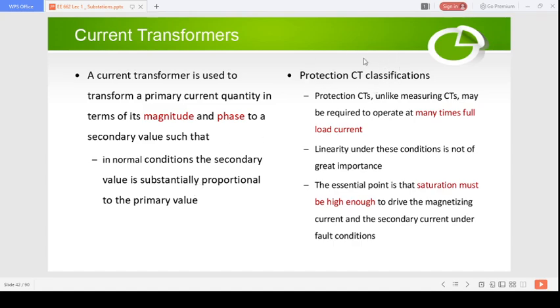Okay, so we can classify the protection CTs. Unlike the measuring CTs, the protection CTs may be required to operate at many times full load current. So these protection current transformers should be able to measure the fault currents, which are many times the full load current. Linearity under this condition is not of great importance. You don't mind whether the relation is linear or not, but what matters is that you should be able to withstand this current and take the measurements. The essential point is that saturation must be high enough to drive the magnetizing current and the secondary current under the fault condition.